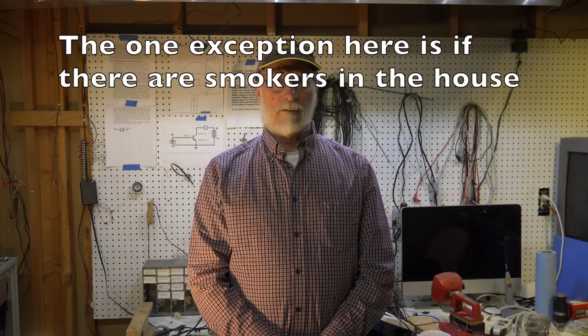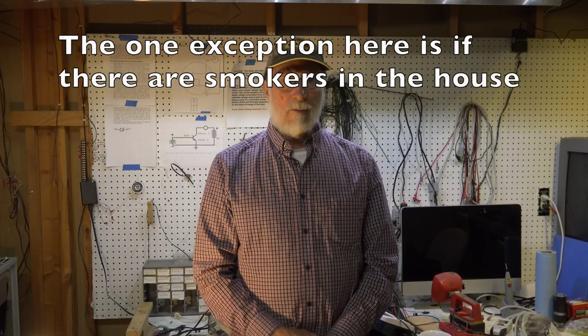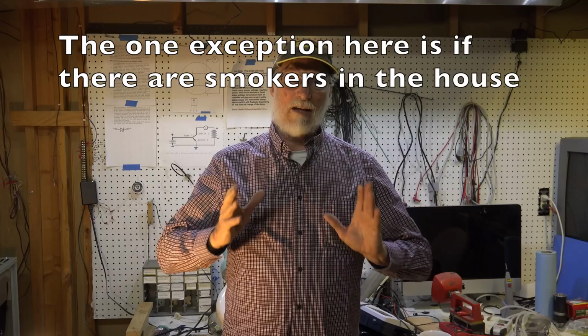I would do that if I had a customer that thought they had a problem, or for some reason I thought there was a problem. I would come into the house after setting the CO detector and see if I got any reading at all. Any reading at all, I've got to find it. If I got 3 parts per million, you really should not have that in a house. So the next thing I'm going to do is go down to all the gas appliances and sniff around them a little bit. I'll look for draft hoods that may be dumping, something like that. Water heaters still have draft hoods on a lot of them. I'll be looking for those sorts of things.